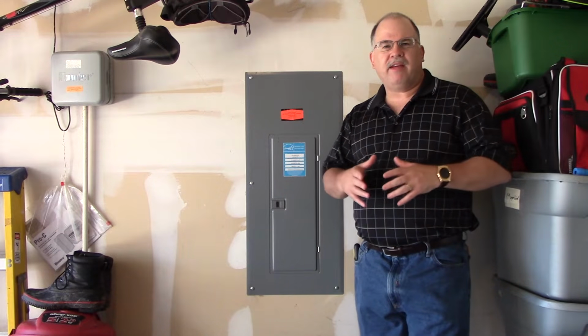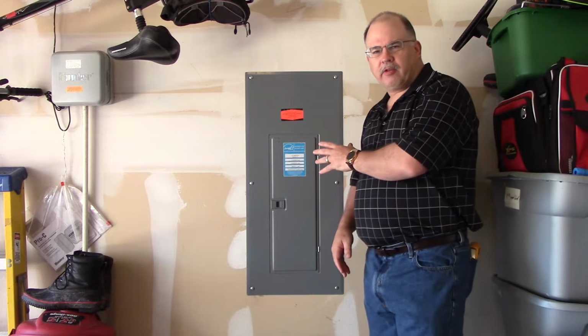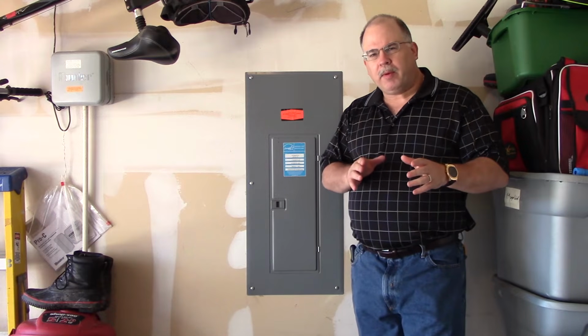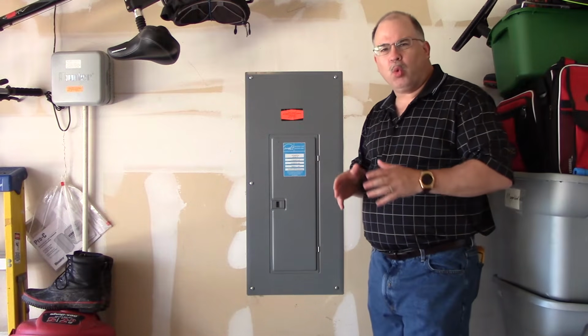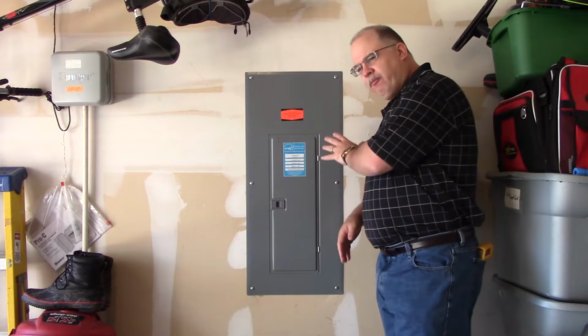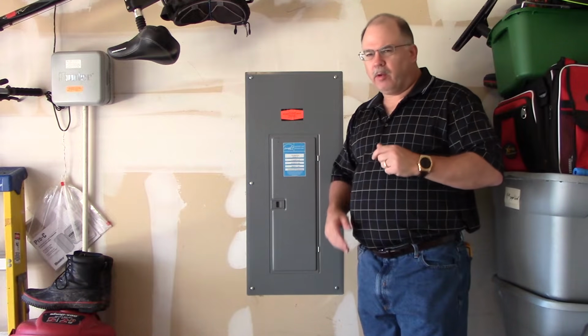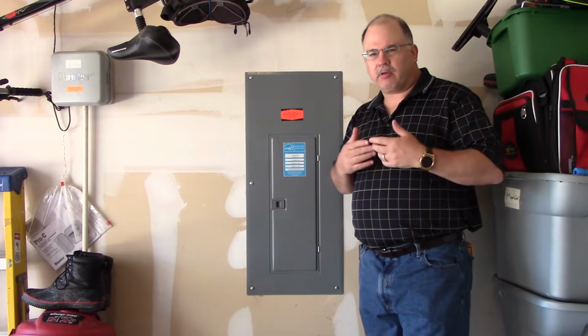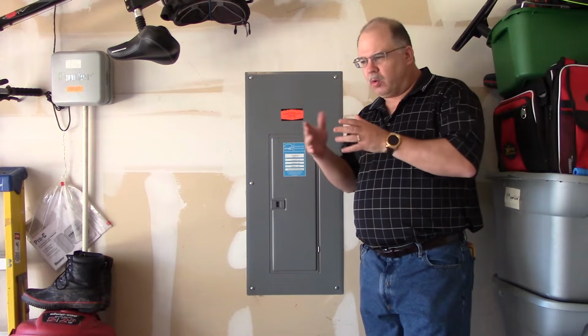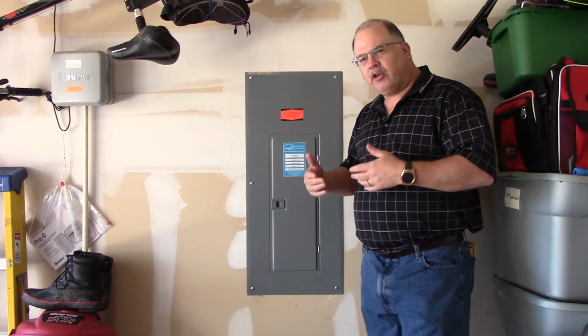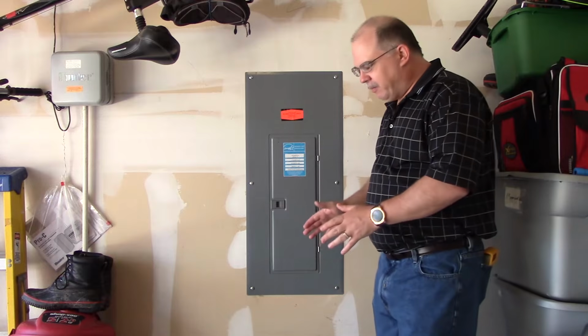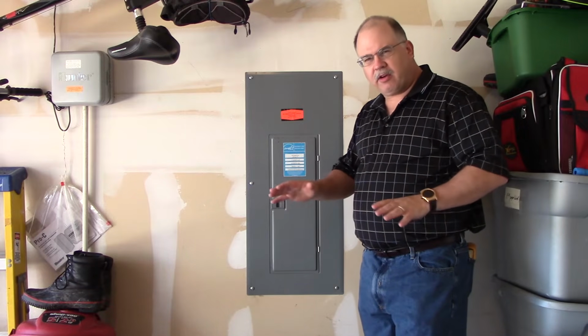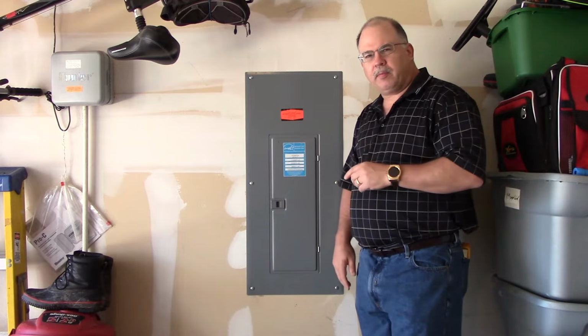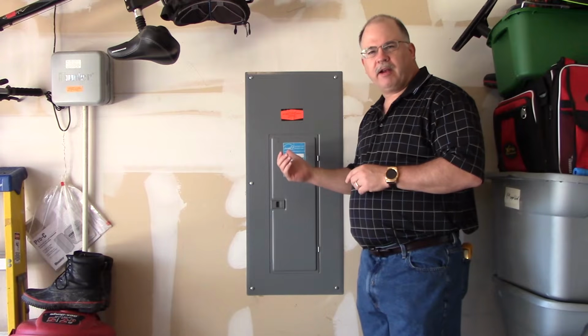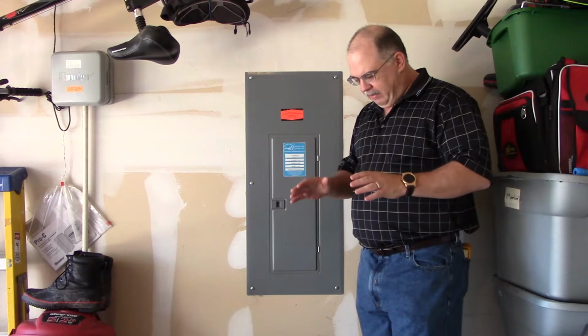Okay. Now we've got to the point where we're going to start looking at this electrical panel. The first thing we want to remember is that we have to have adequate working clearance here to work on this panel. Now, whether you're an electrician, electrical inspector, or a municipal inspector, or a home inspector, your client also as a home inspector needs to make sure that they maintain this nice clear space to get access to this panel.